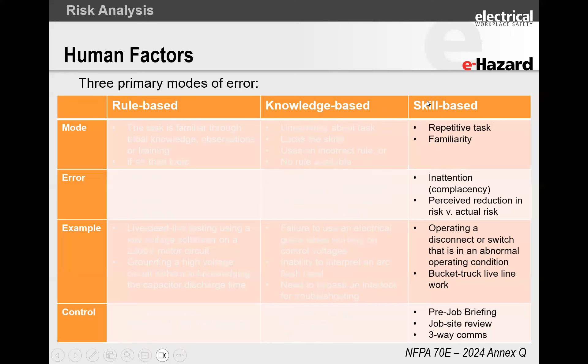The last error type is the skills-based error. It's like bag of potatoes — repetitive. I take it off the truck, throw it on the conveyor, take it off the truck, throw it on the conveyor. I bypass the interlock, open up the MCC bucket, hit the reset button, and move on. This is one of the biggest ones we try to address through human factors — we become complacent. We don't know what the actual risk versus the perceived risk is. That is switching a disconnect. How many of you have switched a disconnect without giving it a second thought? How many have forgotten the one-hand rule and to stand to the side because 'it's just a 30-amp disconnect'?